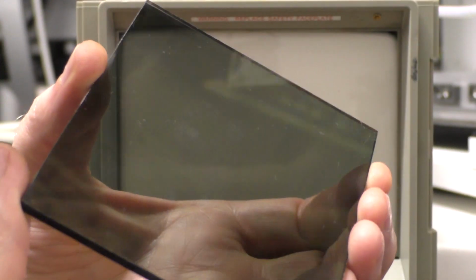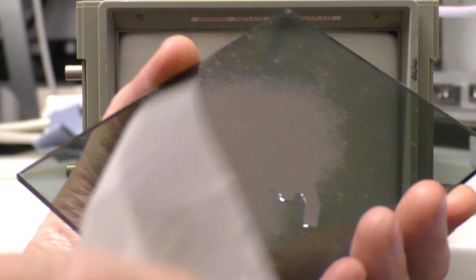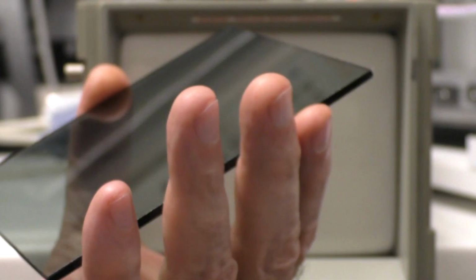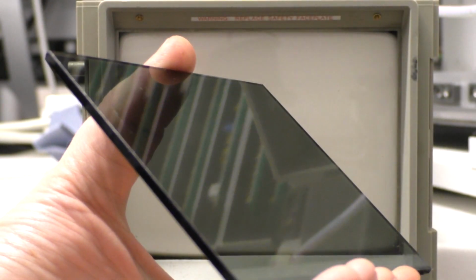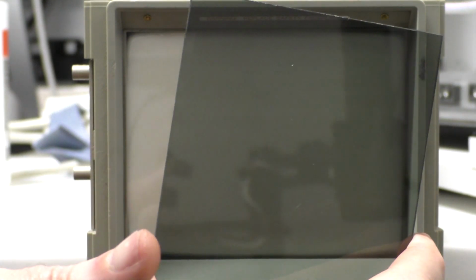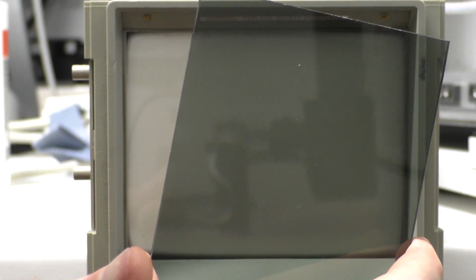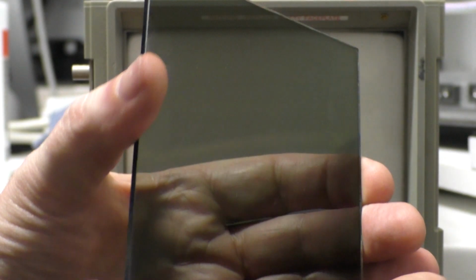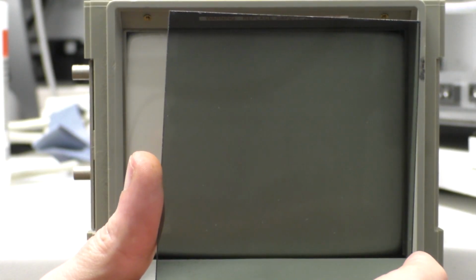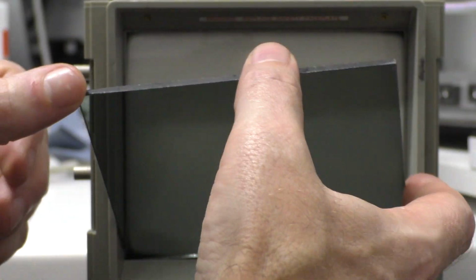We can see some further residue on the cover. This will need some additional force, but be careful as there is a non-reflective coating on the outside of the cover. Once clean and streak-free we can remount the cover. We can see here that one side is more reflective than the other. Ensure the non-reflective side is facing outward.